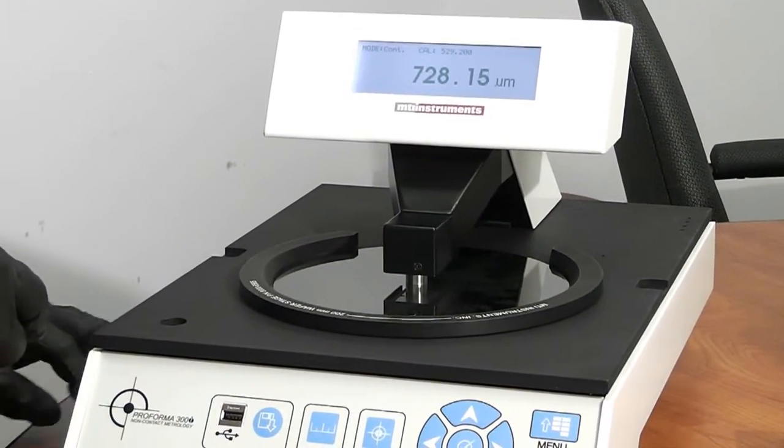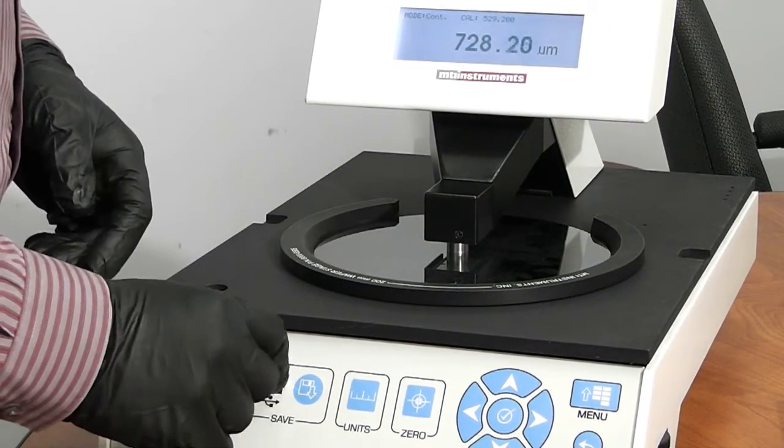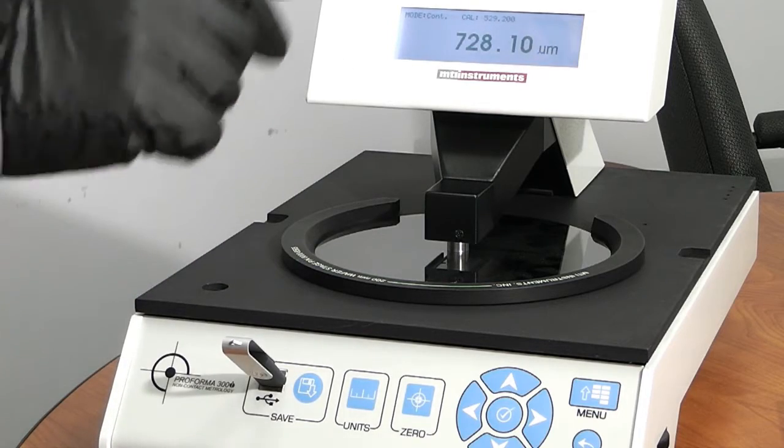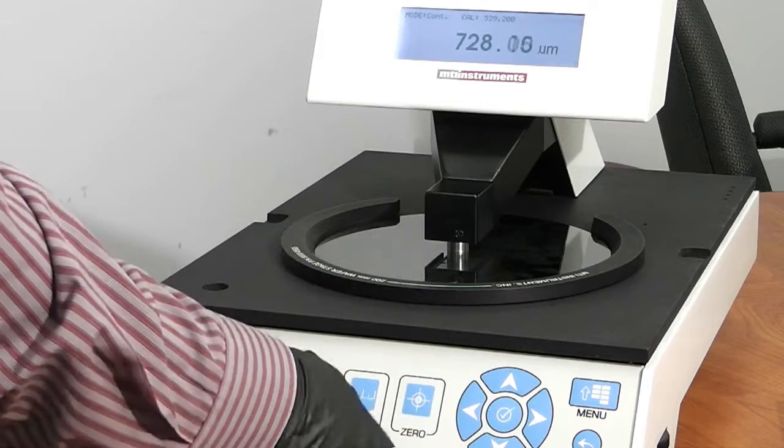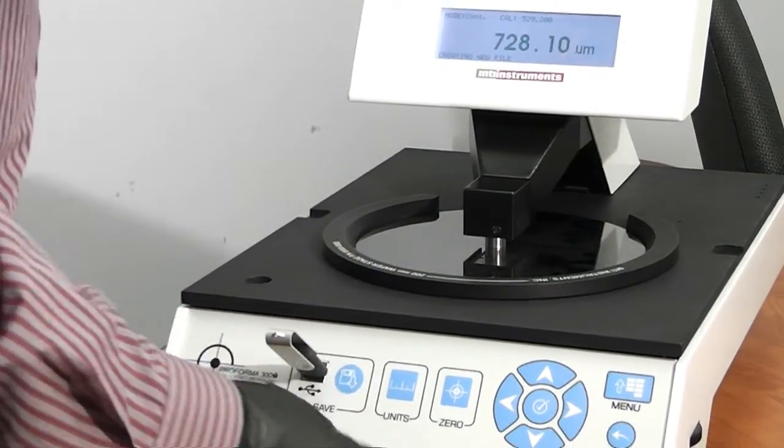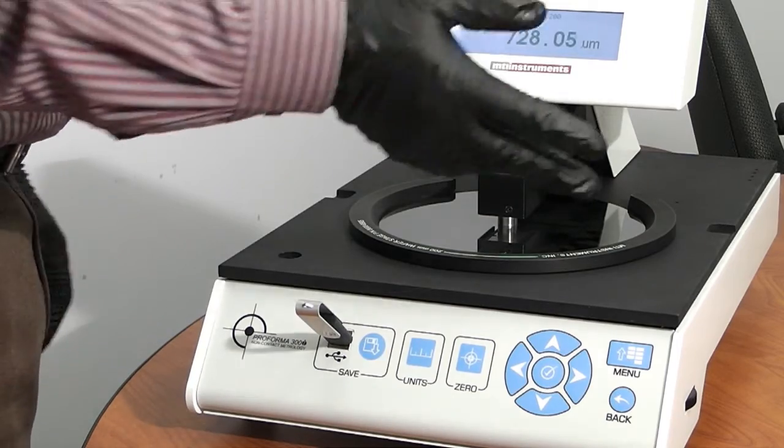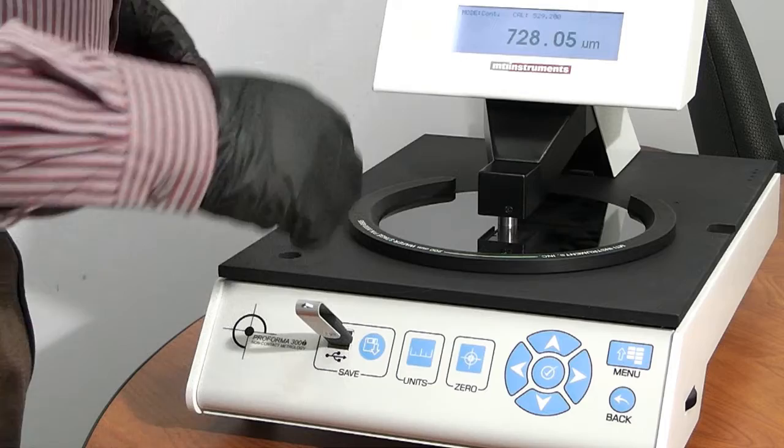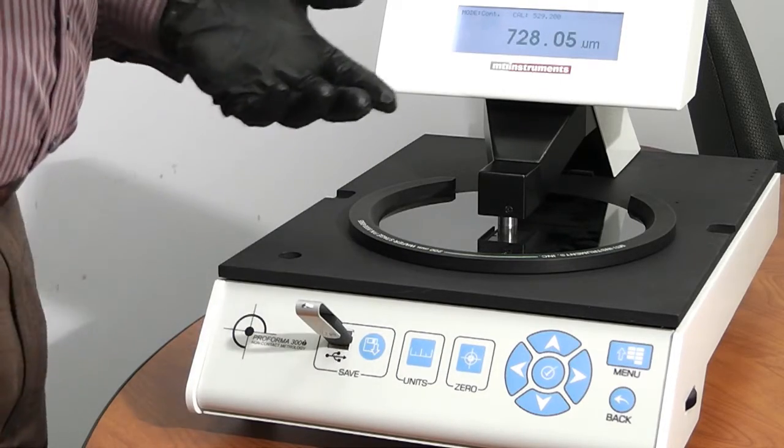One of the other things we can do if we want to record the center point reading of this, we also have a feature here. If we put a thumb drive in, and we've set this up to export our data to a USB thumb drive in the setup menu, all we have to do is hit the save command here, and you can see saving data. So if I wanted to measure, say, 300 wafers, every time I measure a wafer, I press the save, and then it gets written to the thumb drive, so we have a record of that.